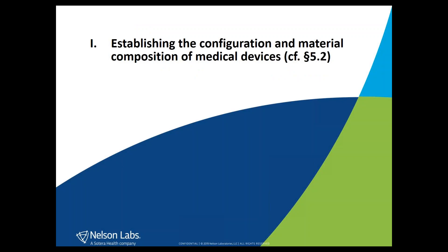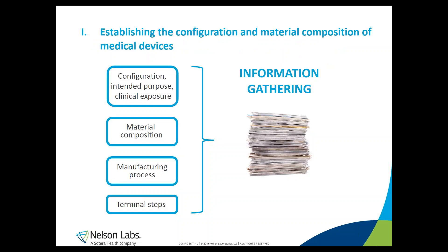In the first step, you will have to establish the configuration and material composition of your medical device, as described in paragraph 5.2 of the final draft. You will need to understand your medical device: its configuration, how it will be used, the intended purpose, and the clinical exposure — in other words, how many replicates of your medical device can be administered to the patient in one day. You will also have to describe the material composition and understand the impact of your manufacturing process, including which residues could remain after processing.